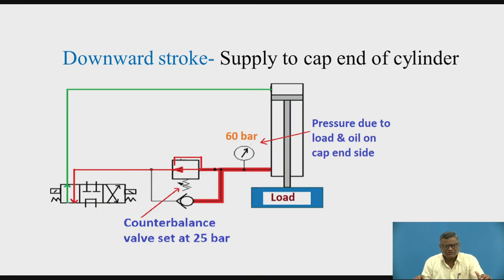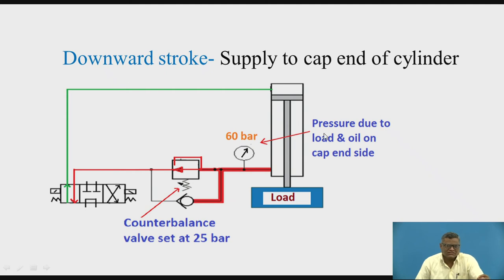Now we are shifting the spool. When the spool is shifted to this position, P is now connected to A. So the pressurized oil goes to the cap end of the cylinder, and the force will be exerted on the piston. Now the total pressure has contributions from two components: one is the pressure due to the load, piston rod, and piston; the other is the pressurized oil received from the pump on the cap end side. This pressure plus the pressure due to the load together increases, and the value obtained is equal to 60 bar — which is larger than the setting of the counterbalance valve at 25 bar.